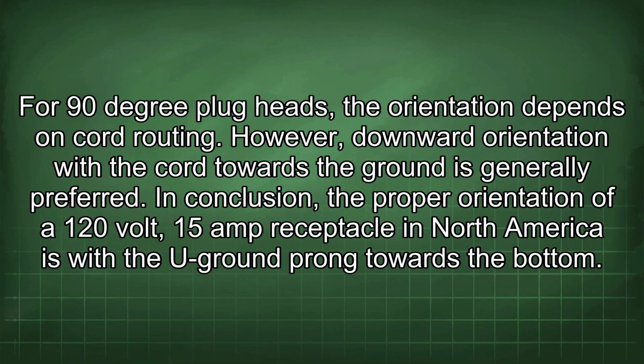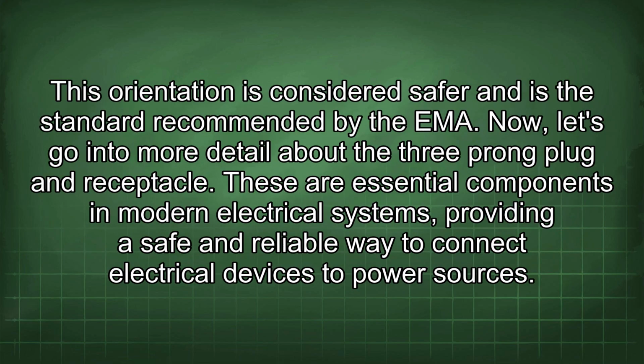For 90-degree plug heads, the orientation depends on cord routing. However, downward orientation with the cord towards the ground is generally preferred. In conclusion, the proper orientation of a 120-volt, 15-amp receptacle in North America is with the U ground prong towards the bottom. This orientation is considered safer and is the standard recommended by the EMA. Now, let's go into more detail about the three-prong plug and receptacle.